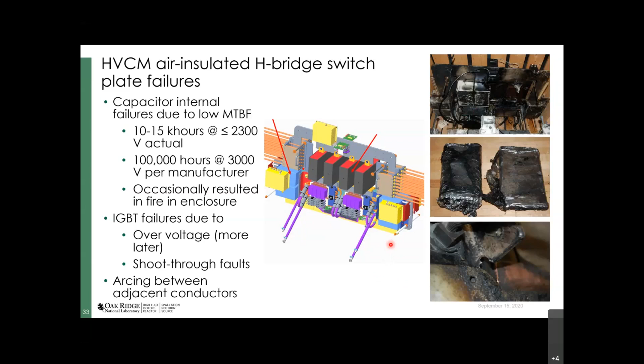Some of these were also associated with the problems with the IGBT, and I'll talk some more about that later. Shoot through, where we didn't have adequate protection, was one example of an instance where we would have an IGBT failure. So one of the things we did is we added the CO2 system, which I described earlier, to mitigate some of the fire events. But since we've solved a lot of problems, these are actually rather rare nowadays.